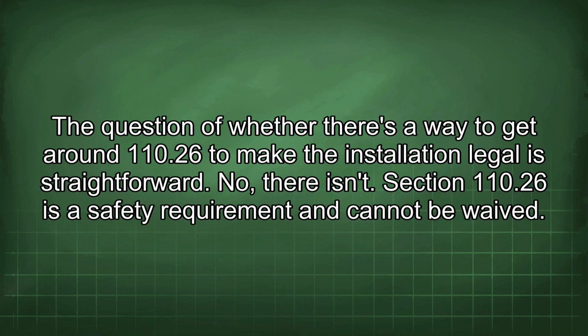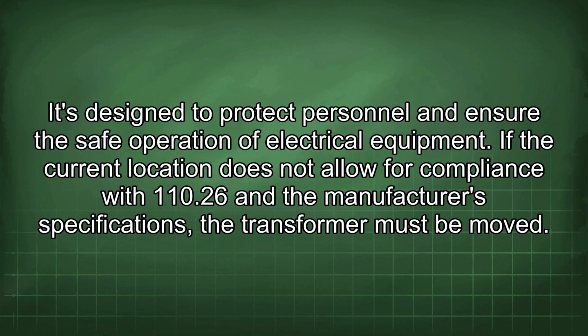The question of whether there's a way to get around 110.26 to make the installation legal is straightforward. No, there isn't. Section 110.26 is a safety requirement and cannot be waived. It's designed to protect personnel and ensure the safe operation of electrical equipment. If the current location does not allow for compliance with 110.26 and the manufacturer's specifications, the transformer must be moved.